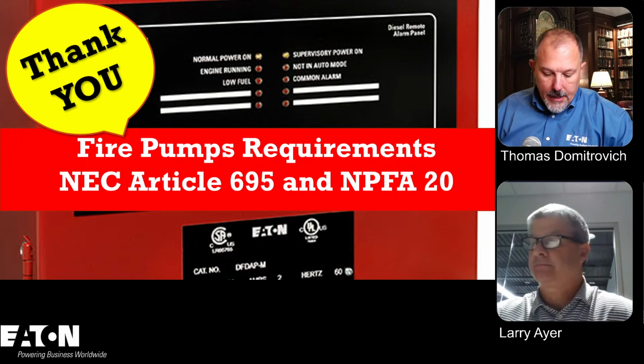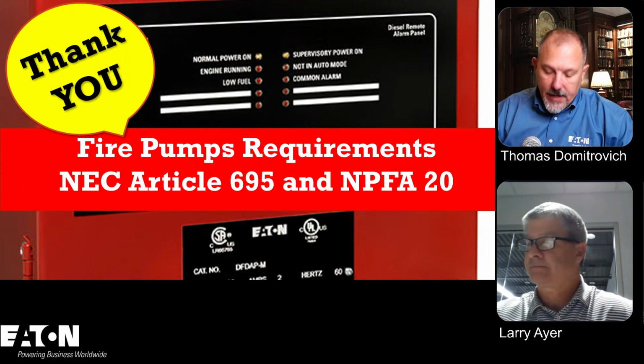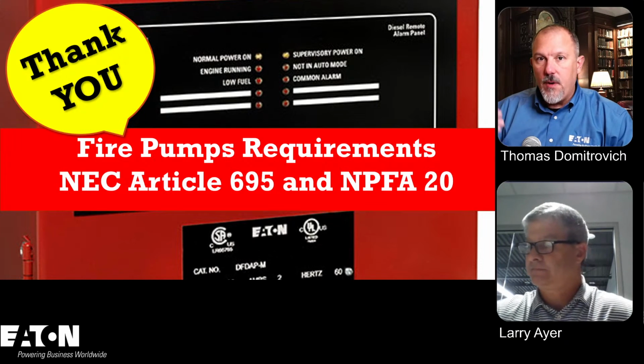Yep. And the other thing, it does say that the transfer of power to the fire pump controller between the individual source and the alternate source has to take place within the pump room.